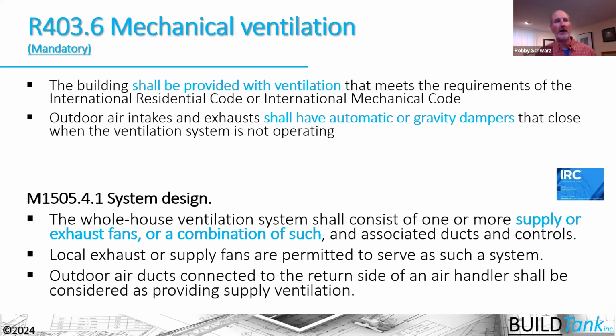If our systems are connected to the air handler, if we have a forced air system, we also have to have an ECM, or electric commutating motor, a more efficient motor on that HVAC system as well. And then we have to remember that in climate zones 7 and 8, you don't have the ability to add a supply or exhaust system. You have to only use a balanced ventilation strategy using an ERV or an HRV.